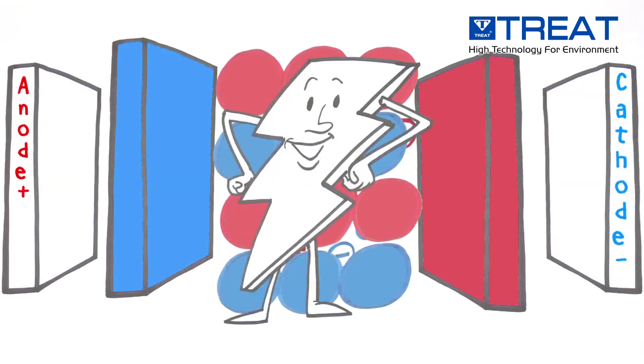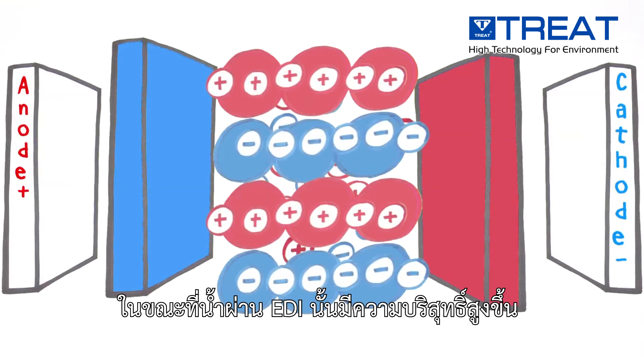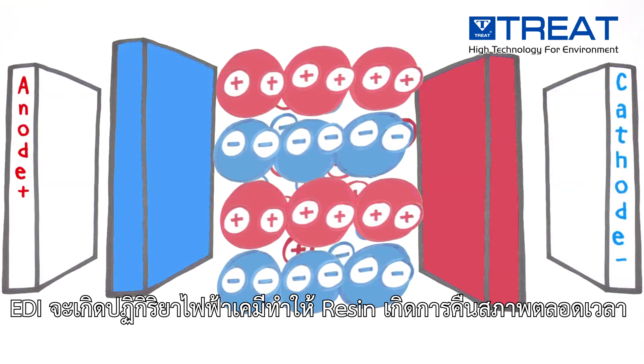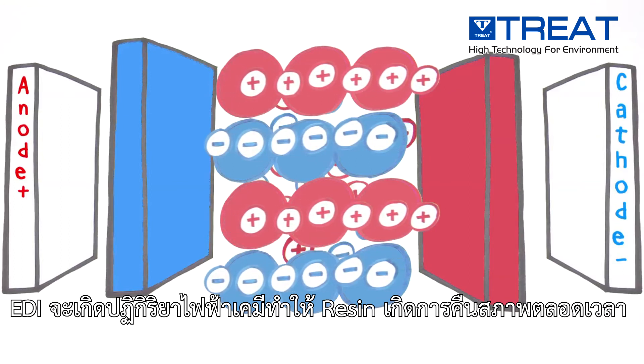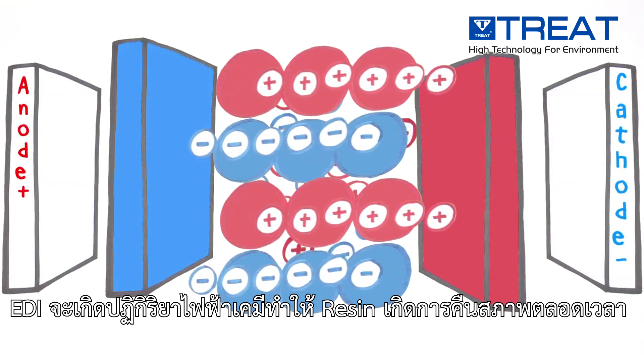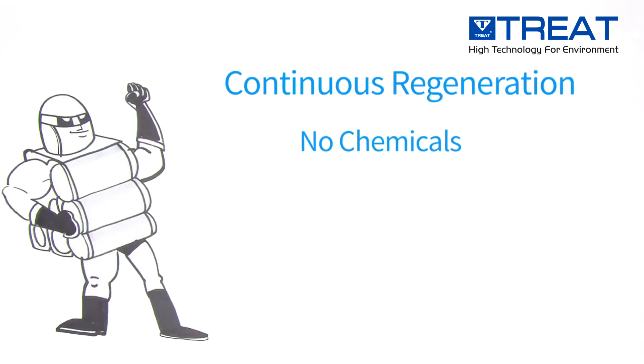To produce high purity product water, as the water passing through the module becomes pure, an electrochemical process takes place that continuously reactivates the resins, creating the chemical regenerants in place — so it is not necessary to handle hazardous chemicals.